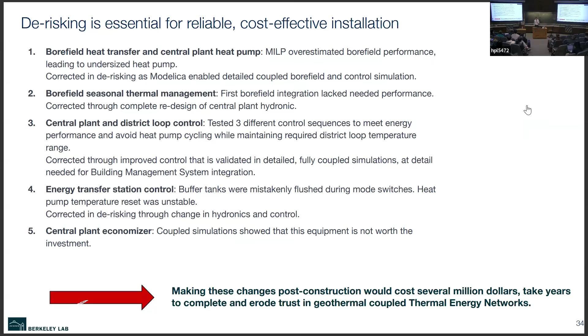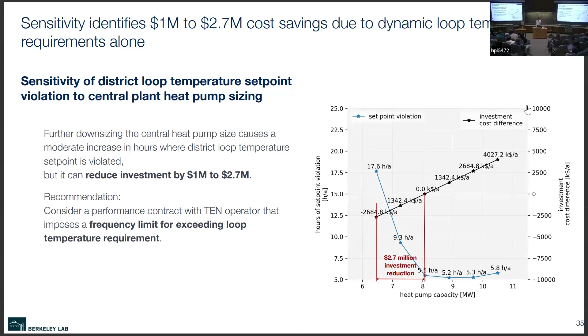Sensitivity studies were also conducted, as I mentioned earlier. We can use the model to play with different design variants, for example seeing what happens if we reduce or increase the heat pump capacity in the central plant, and what that does to investment cost or life cycle cost. Here we identified a cost saving potential of around $3 million by undersizing the heat pump slightly, while still maintaining loop temperatures except for about 18 Kelvin-hours, which is a very small amount.